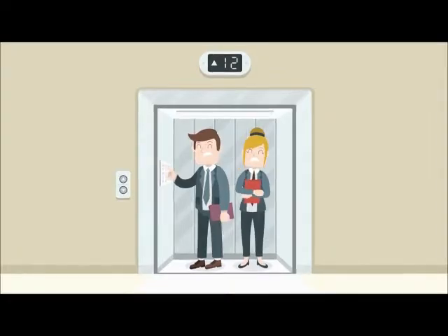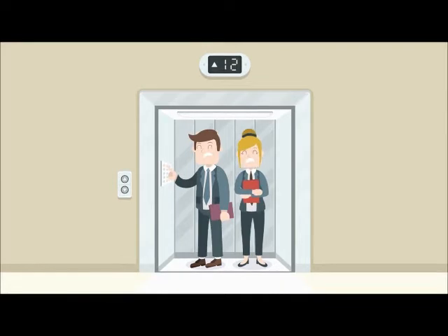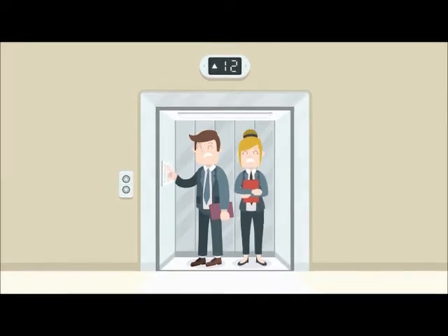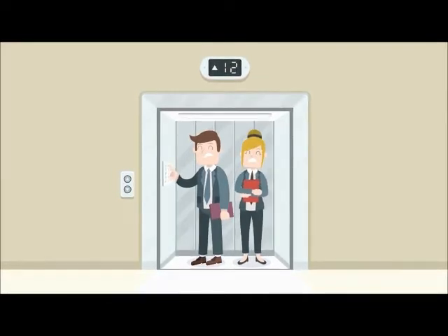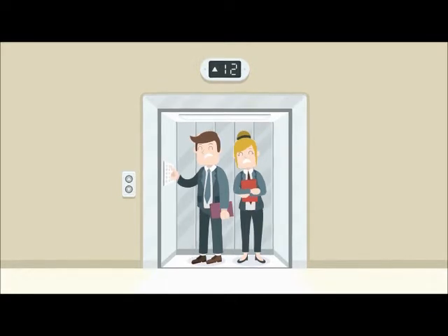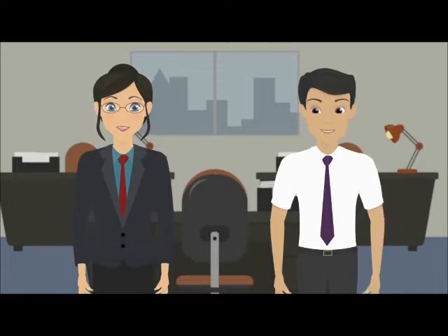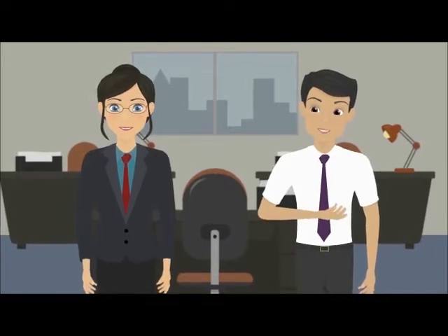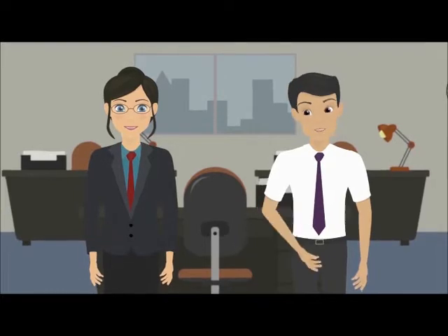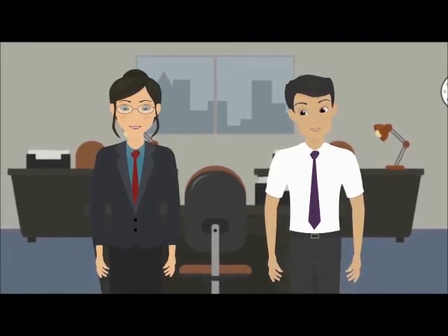If the door sensor wrongly senses someone when no one is there between the doors and opens the closing door, or prevents closing of the open door, then it's safe failure. Oh, that means the elevator door will not close and the car will not move. Absolutely. But safe failure only causes stoppage of elevator, but dangerous failure results in harming personnel.